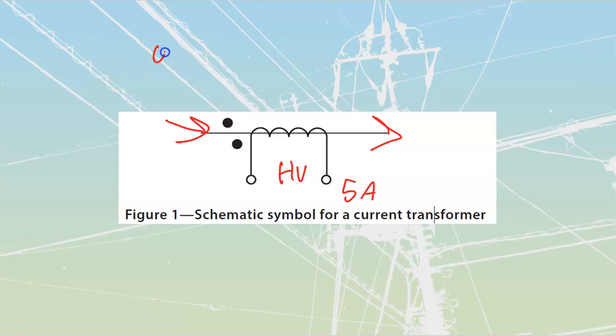We've got classes that are 0.3%. This is not 3%, this is 0.3%, so less than 1%. We're going to have 0.3, 0.6%, and then 1.2%. Obviously, the more accurate you make something, the more fine-tuned your manufacturing has to be, which comes at additional expense, so these ones are going to be more expensive meters.